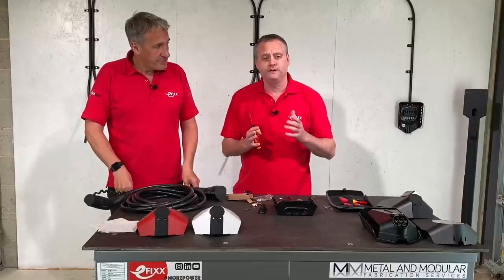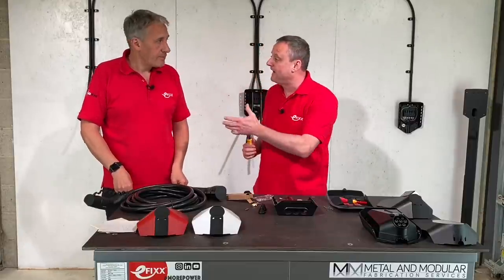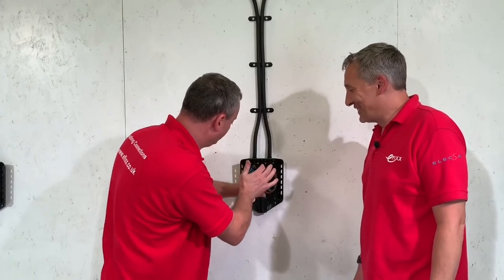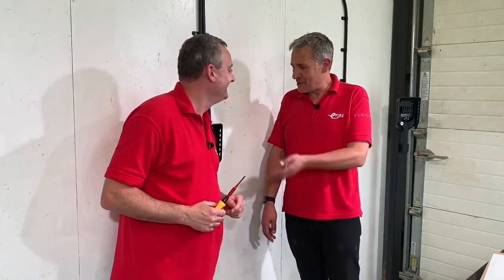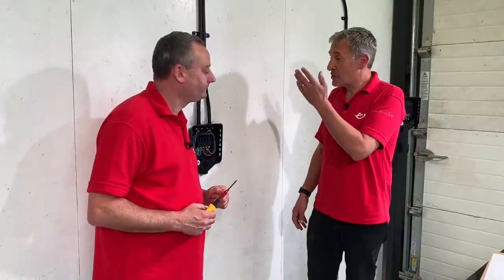Not many people may have the hex bit in their torque screwdriver kit — that's needed to get the terminations back to the required torque settings, which we'll show during the installation. Gary cuts to installation footage showing the torque going up to the five newton metres required in the instructions. Gary completed the full install alone and had to learn the intricacies of the system.